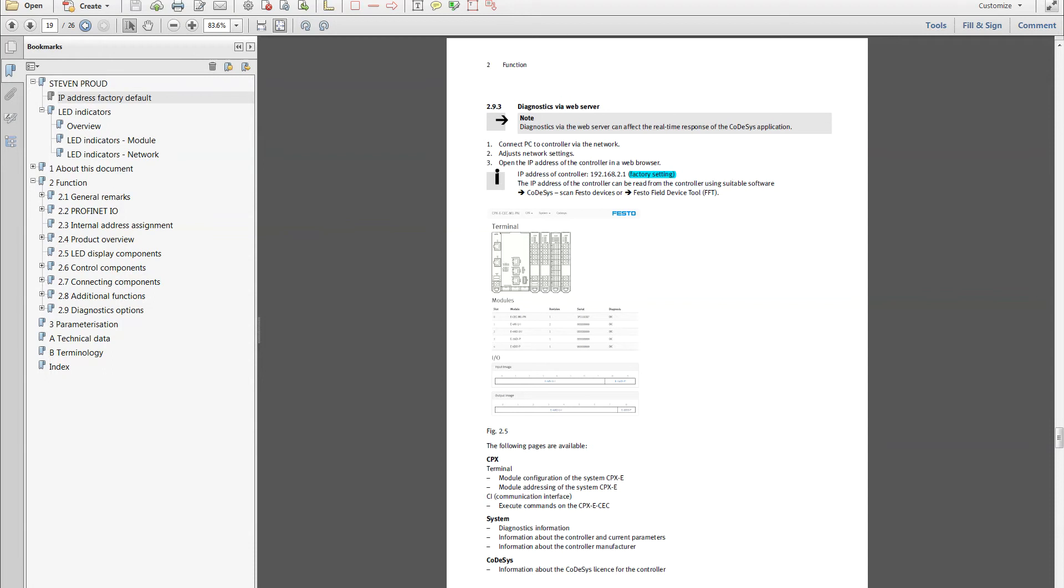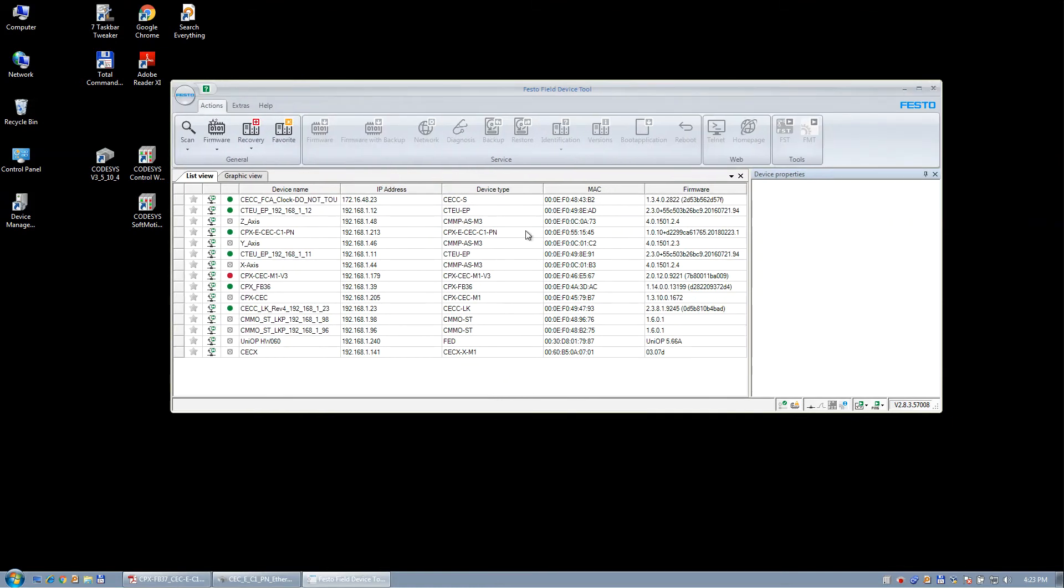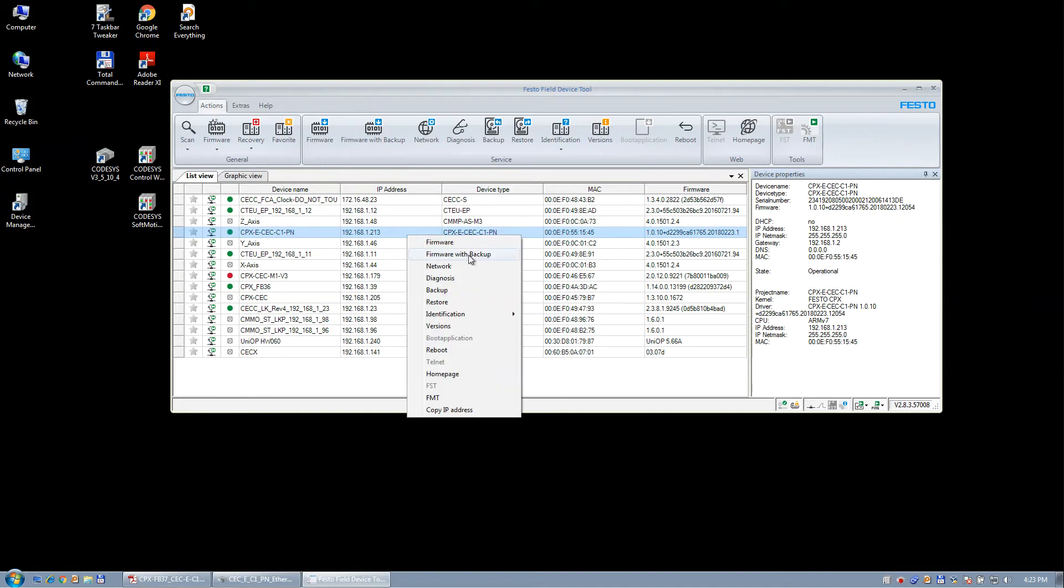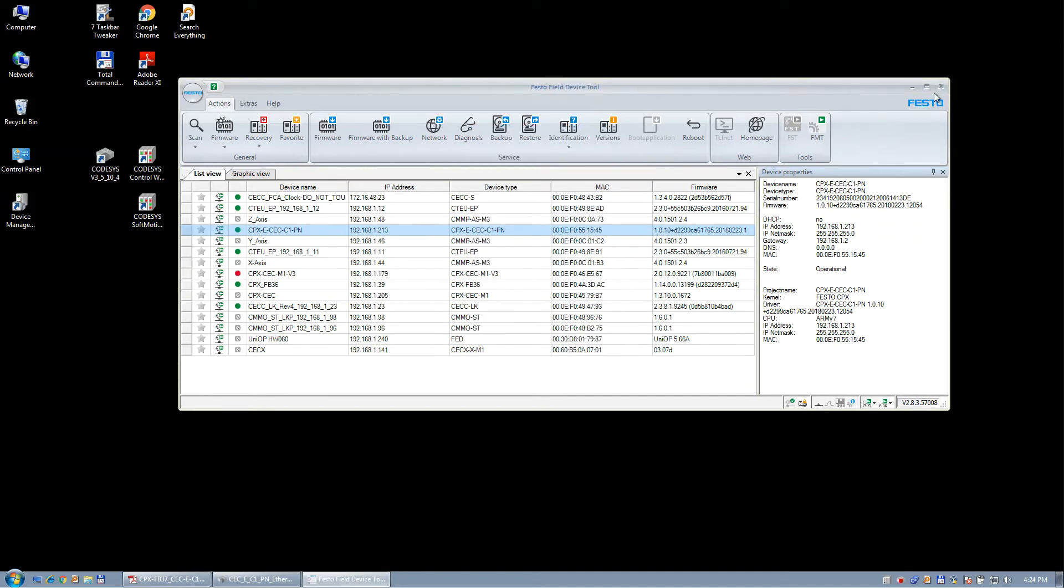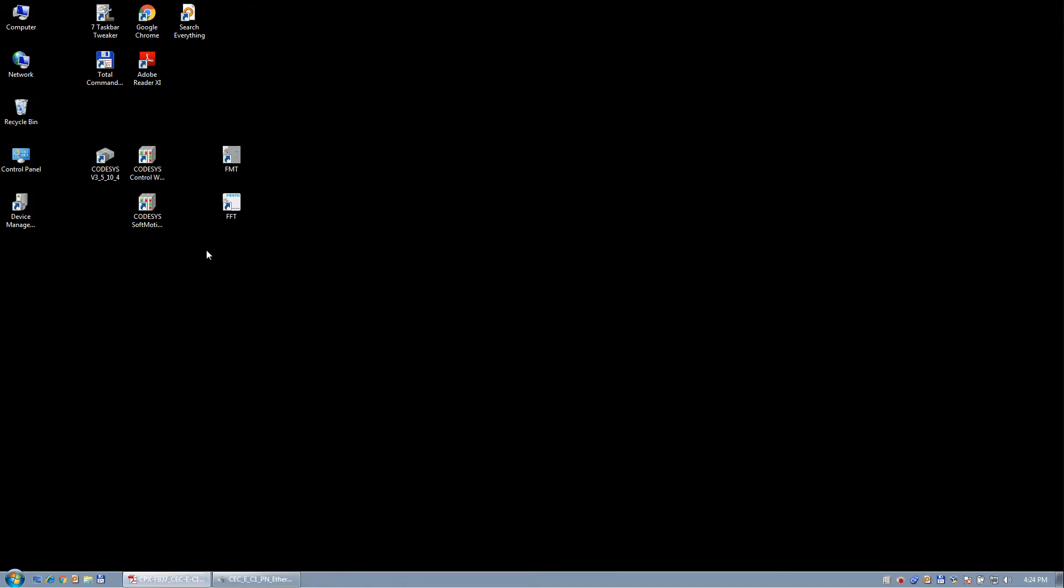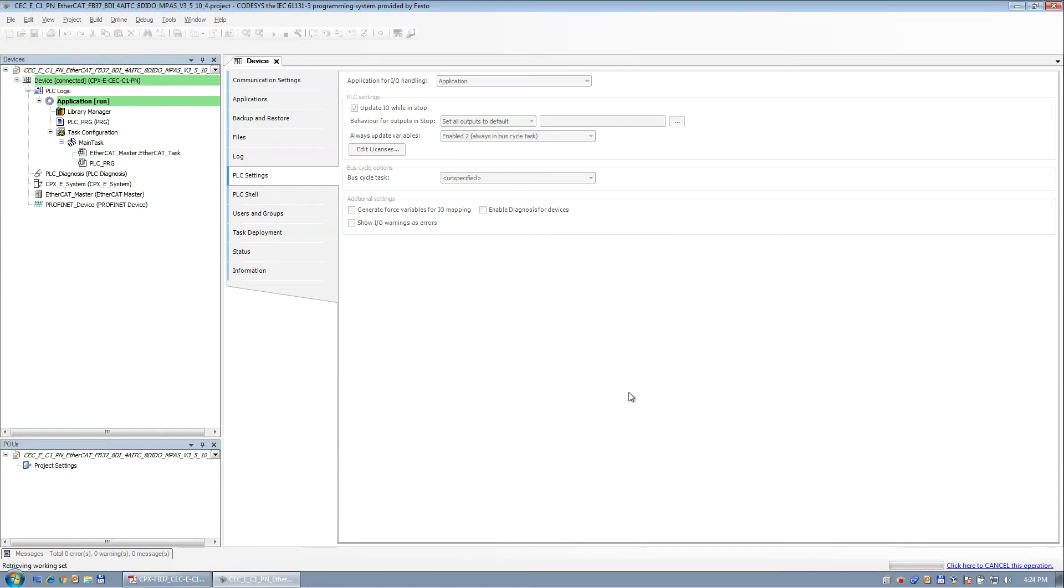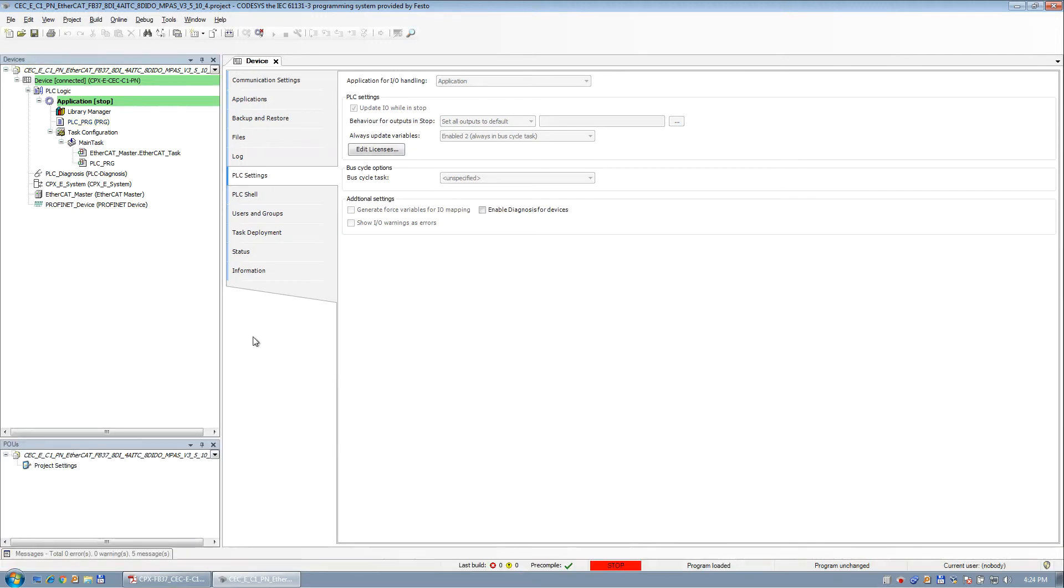And so if you go into the user manual for the CPX-E-CEC, you'll find that the factory setting is 192.168.2.1, which is the factory setting. And if you download the Festo Field Device Tool and scan the network, you'll see that you get this right here. And then you can right-click, put a network, and you can modify the IP address to something that's on your actual subnetwork. I've already done that previously. So now we've scanned the network, and I'm going to dump the program in so that it's got a base.